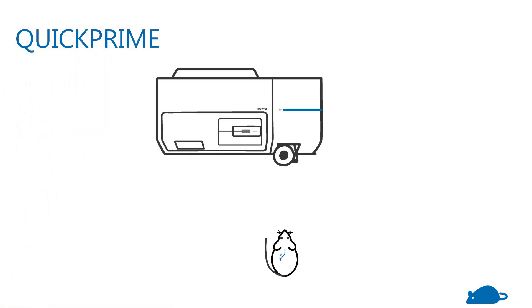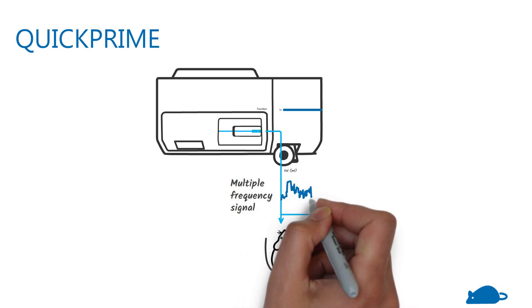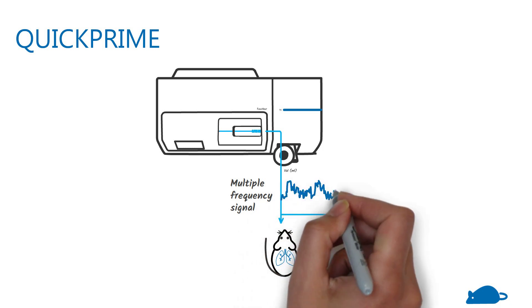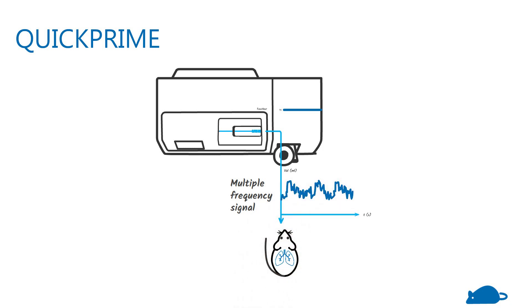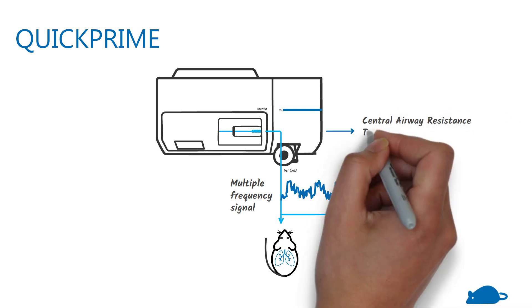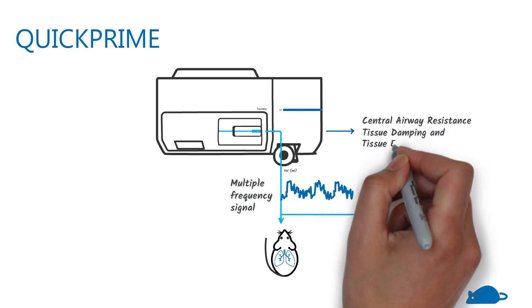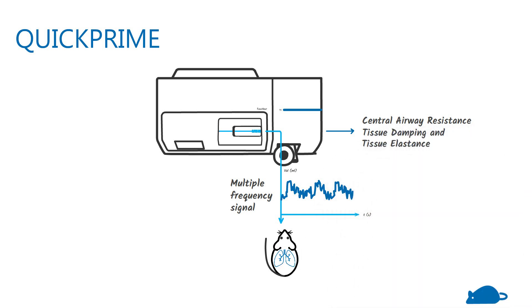In the quick prime measurement, the lungs are given a multiple frequency signal above and below the subject's respiratory rate. The flexi-vent can then separate the contributions from the central airways and peripheral lung tissue to give central airway resistance, as well as tissue damping and tissue elastance.